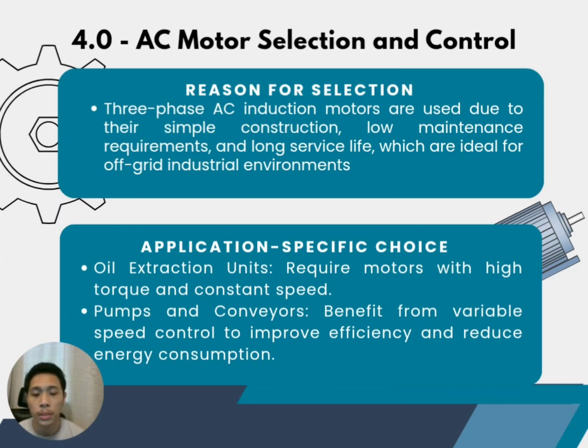Okay, for AC motor selection and control, for our facility, we standardize on using 3-phase squirrel cage induction motors. Why? Because in a remote, off-grid location, we need motors that are rugged and require minimum maintenance. For our specific machines, we choose the motors based on the work they do. First one is for oil extraction. We need high torque and constant speed. This is because crushing a palm fruit is heavy work. The motor must be strong enough to keep a steady pace without slowing down under the heavy load.